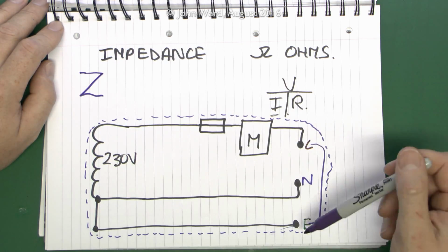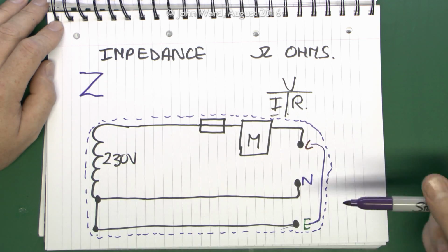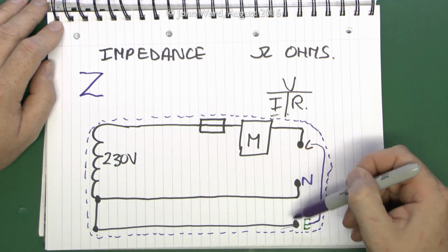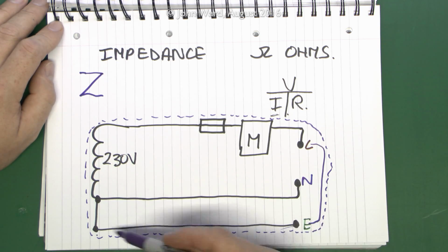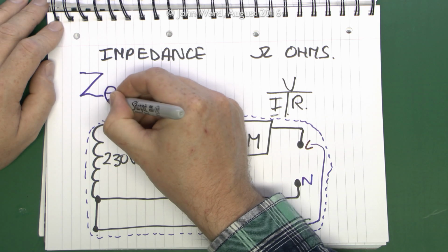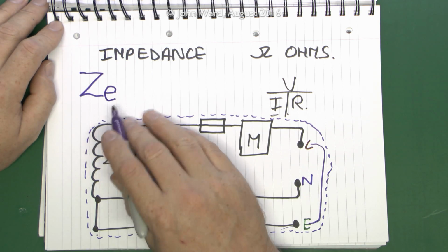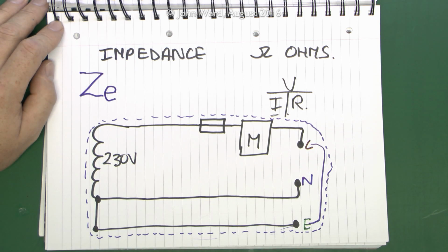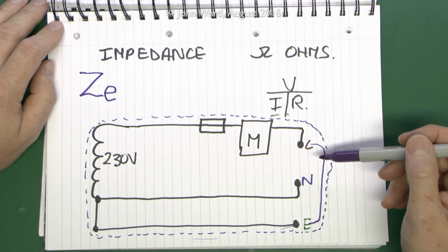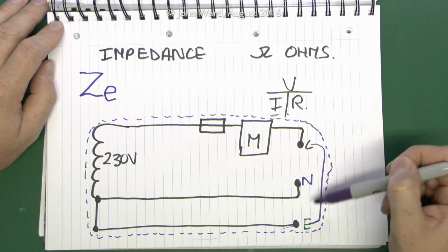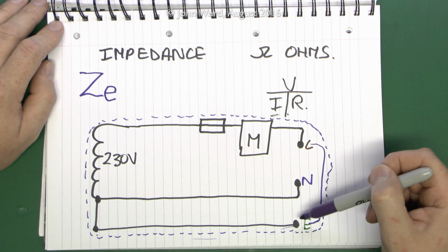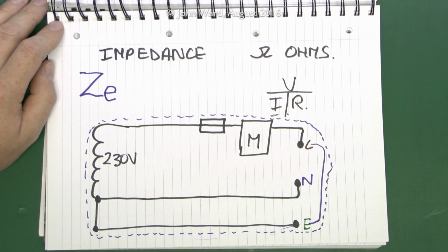And this is what's called the external loop impedance, because bearing in mind this is where the wires are coming into your building, so all of this is external to the installation or outside, and that's given the symbol ZE. So E for external, fairly obviously. And in a real situation, if this occurred at the installation origin here, where the wires come into the building, then of course that is the value which would determine the current that flows.